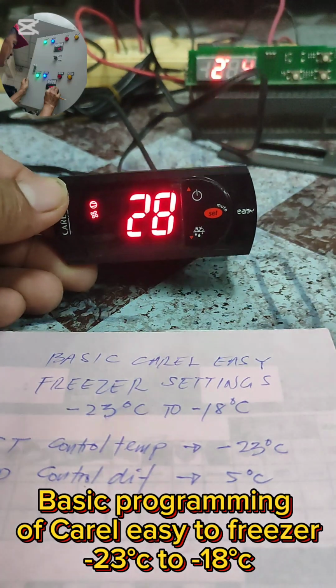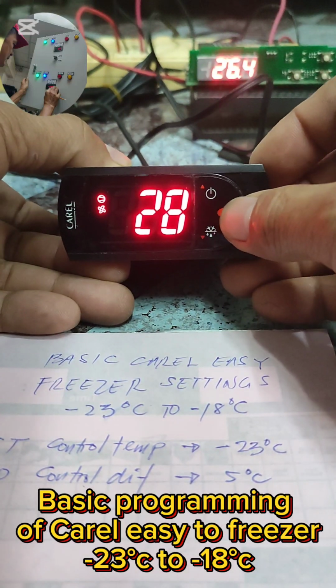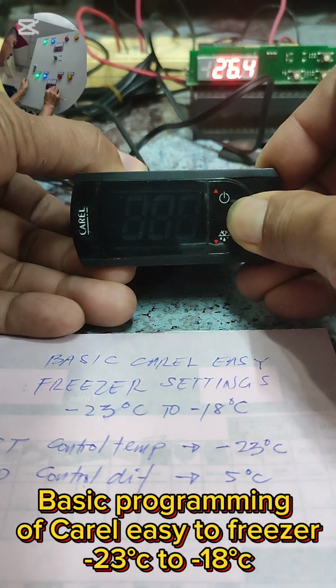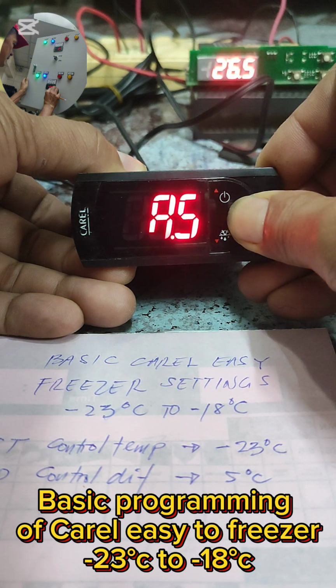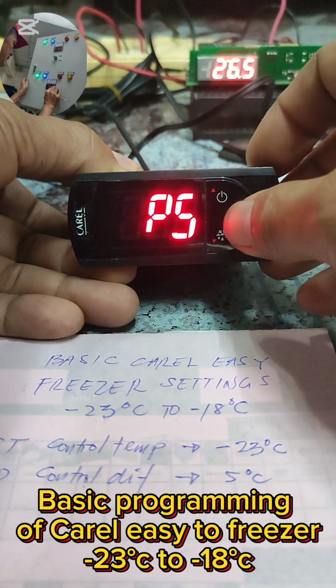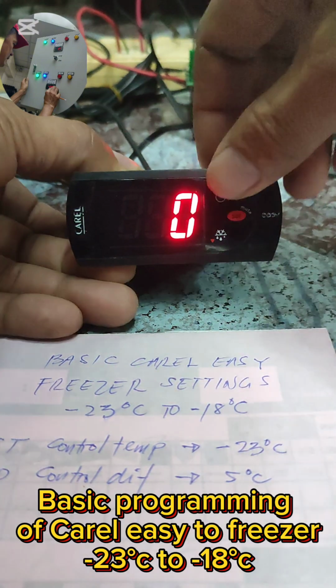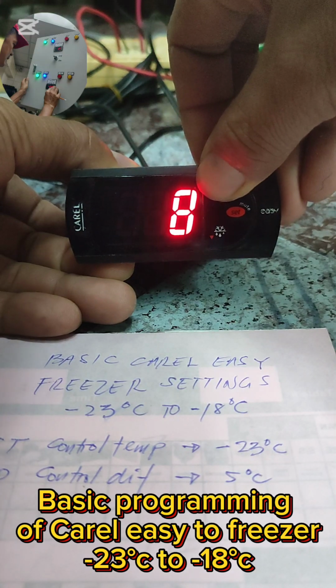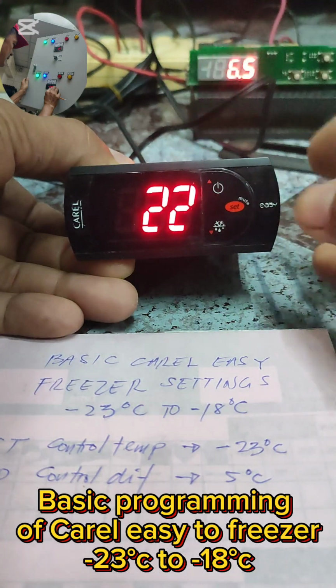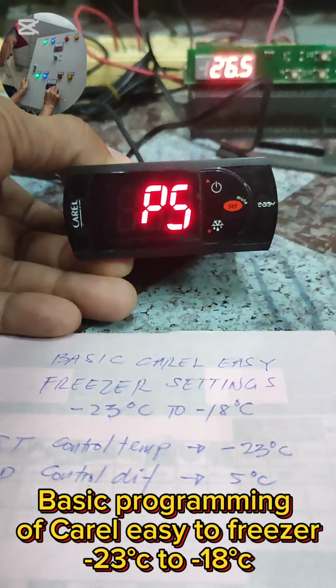And we're going to set this because it's being set to chiller setting. To do that, just long press the set button here. When PS appears, release, then press set again, and we're going to enter 22 for the value of the password.